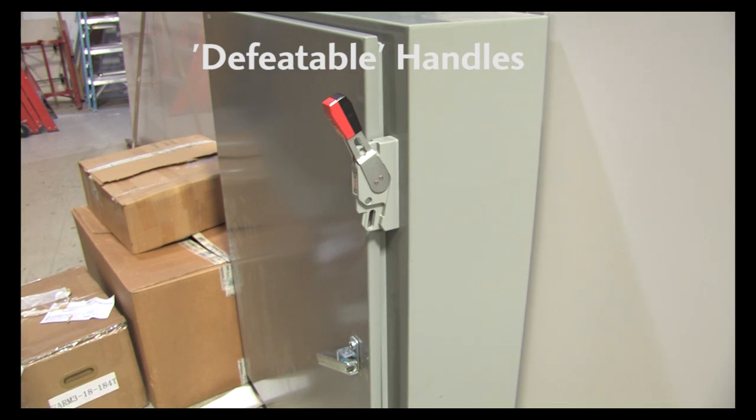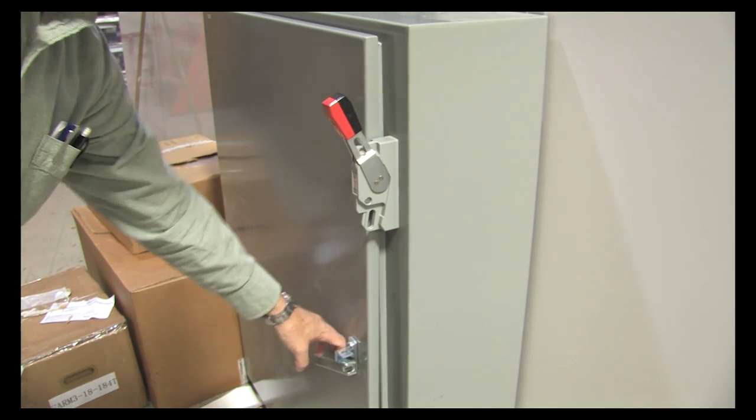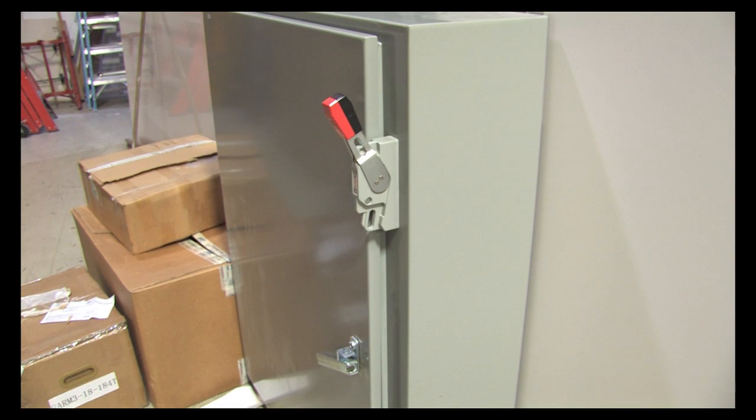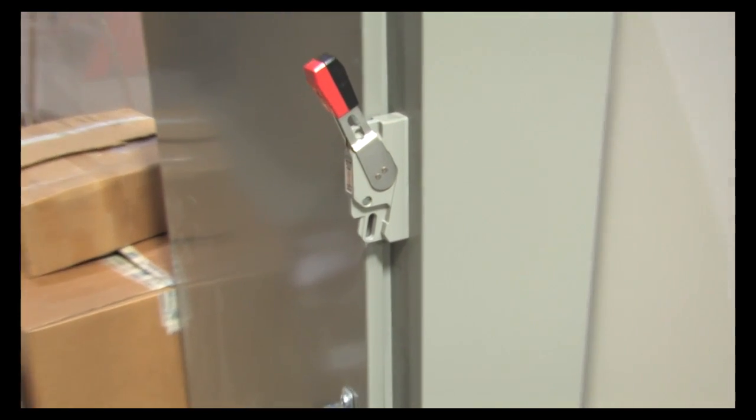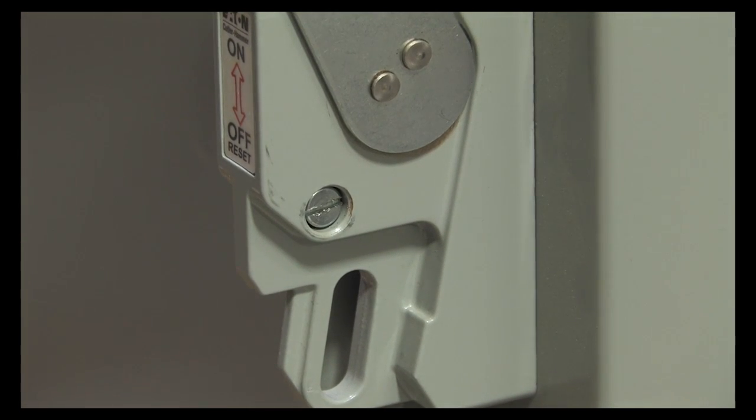Note that some of these are referred to as defeatable. Normally the switch won't allow you to open the cabinet until the power is off. There are times though when it is necessary to access the cabinet while the power is on. Maybe you need to do some diagnostics or some testing. In that case these are designed so you can bypass or defeat the normal operation of the switch. On this one you stick a screwdriver in here and twist and it releases the catch so you can open the door.